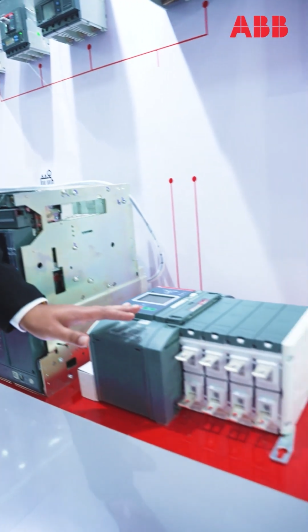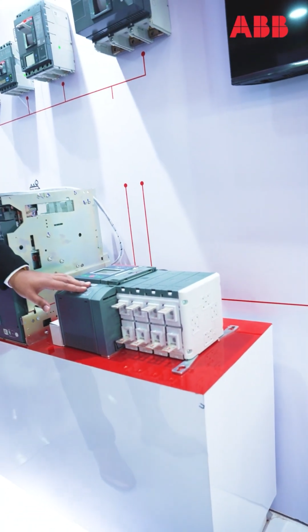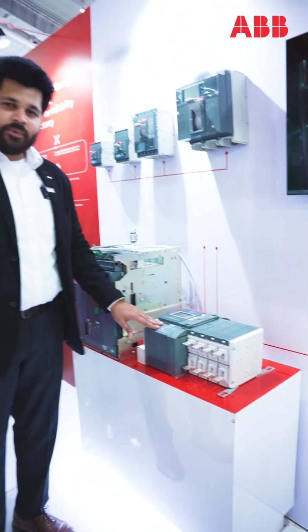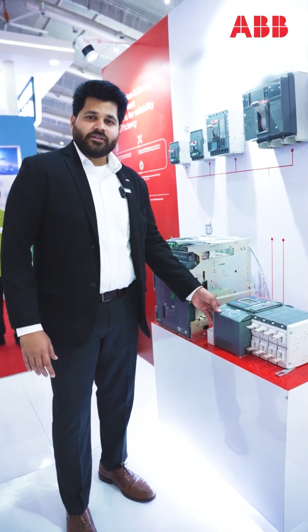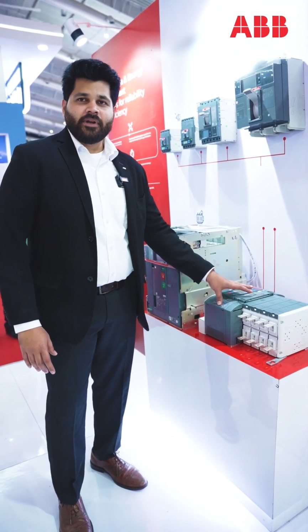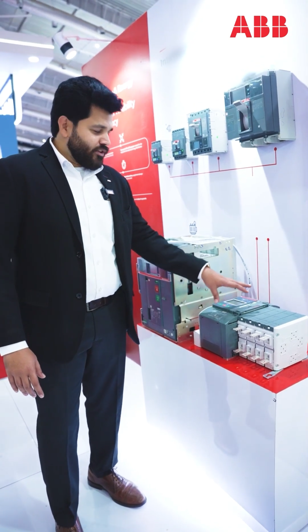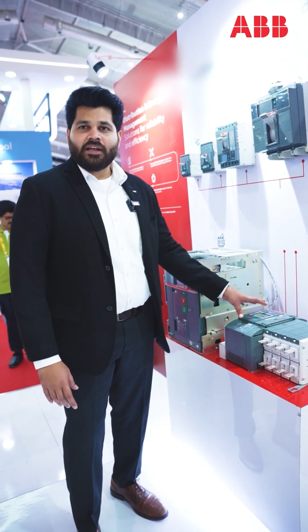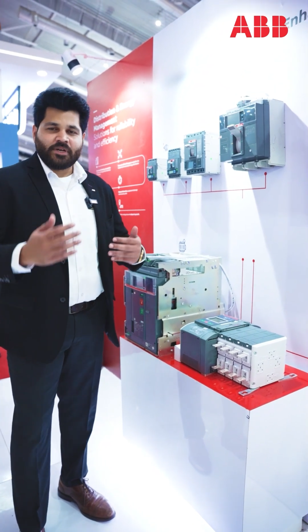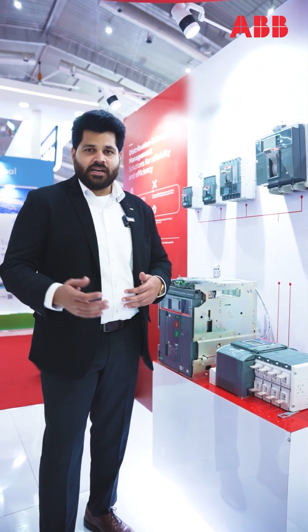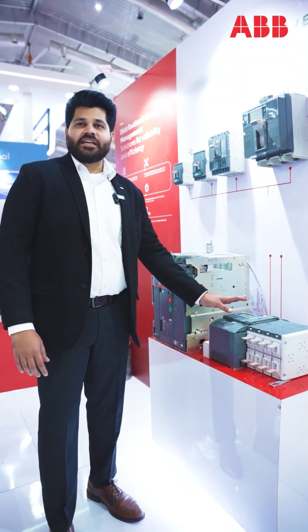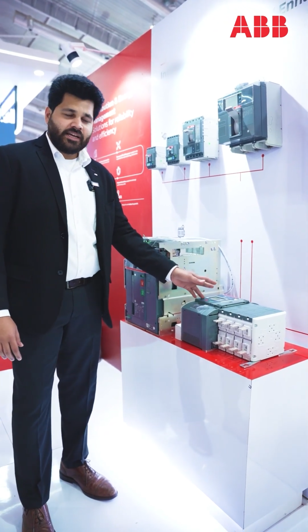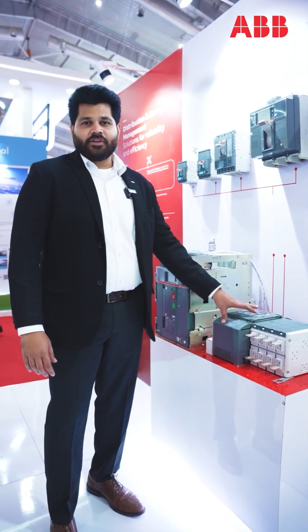And here we have the latest generation of automatic transfer switch. We call this a true one, the reason being the controller is embedded inside the automatic transfer switch. So this operates as a solenoid operated switch with different levels of controllers, which will give you different levels of measurements and also different levels of functionalities. This has the fastest transfer time of less than 50 milliseconds, and also a neutral overlapping feature.